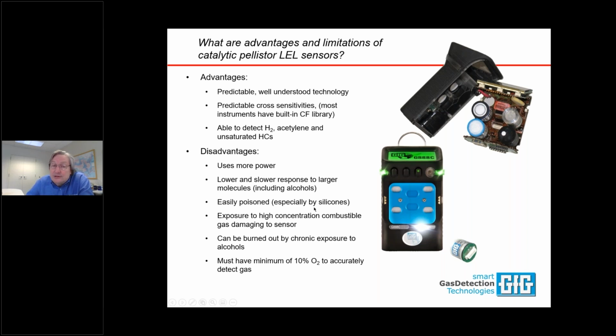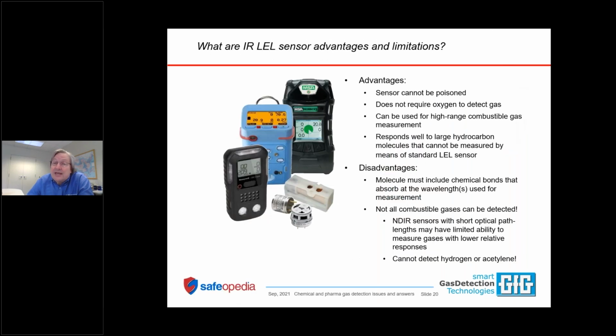And it's easily poisoned by silicones and by methanol. It can be burned out by exposure to alcohols, and it needs at least 10% oxygen in order to detect gases correctly. For IR-LEL, again, you have advantages and disadvantages. Here you can see a full-sized IR-LEL sensor.